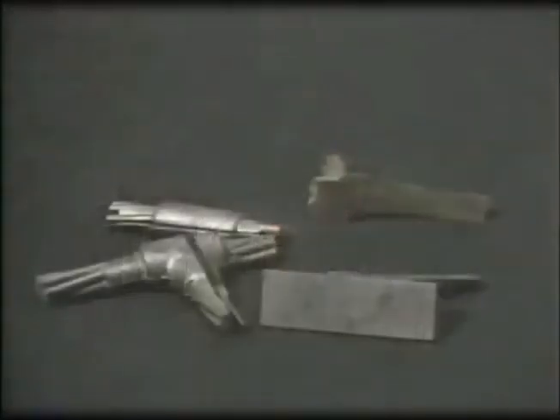Ultimately, good grounding depends on good bonds. Bonding makes those low impedance connections between conductors. Because of their permanent nature, exothermic welds are preferred over clamps in making the connection of the ground rod wire to the ground rod. Here's a demonstration of exothermic welding.